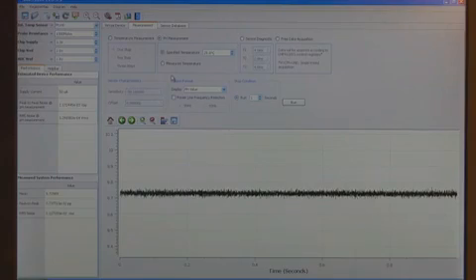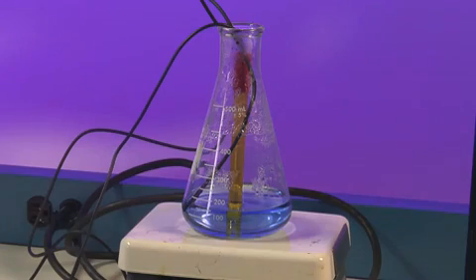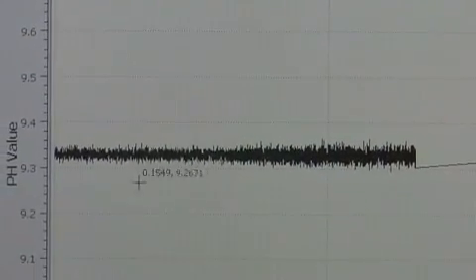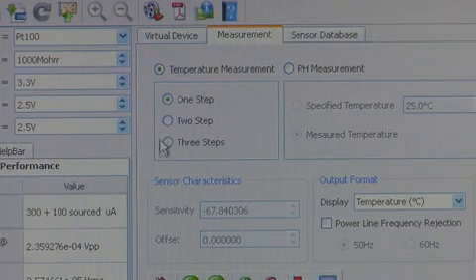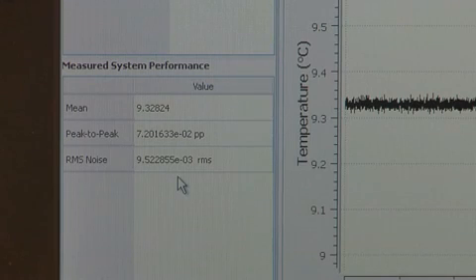Now let's click the measured real-time temperature button. The device will use the RTD in the liquid bath to get the actual temperature. Click run and this will deliver a more accurate pH measurement — in this case, 9.3. If you want even more accuracy, choose the two-steps or the three-steps algorithm depending on your accuracy needs. The tool will walk you through this. On the left of this panel, you see that the tools show you the measured system performance, which includes mean and noise performance too.